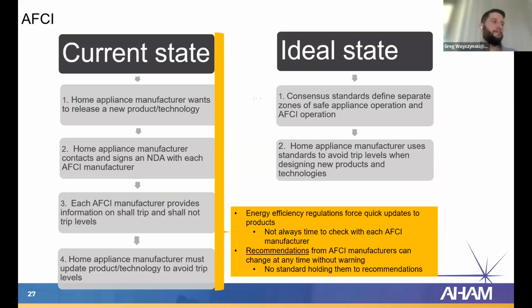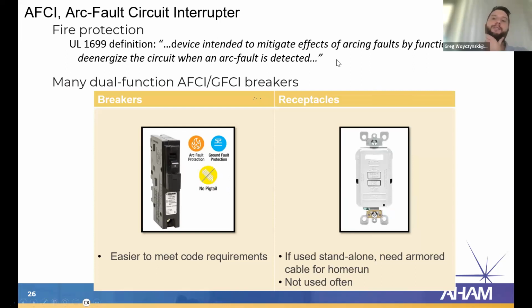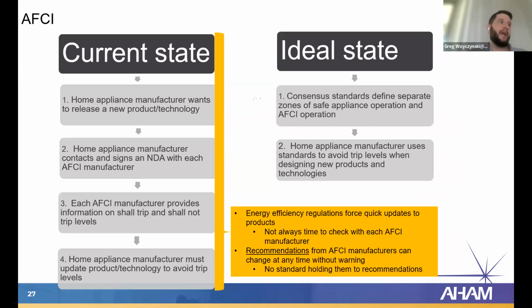So AFCIs are in an even worse state than the GFCI, unfortunately. The AFCI doesn't have a set measurement that it has to trip on. When we looked at the GFCI, we saw that it has to trip on some kind of measurement related to ground current. Well, for AFCIs, each AFCI manufacturer can choose their trip criteria and their trip measurements. So if one AFCI manufacturer wants to base their trip requirements on voltage, they can do that. If another wants to base them on current, they can do that. Both are allowed. The big problem here is that AFCI manufacturers don't make their trip thresholds public.